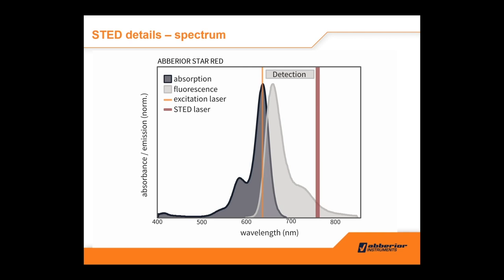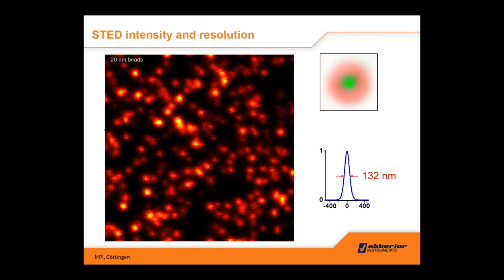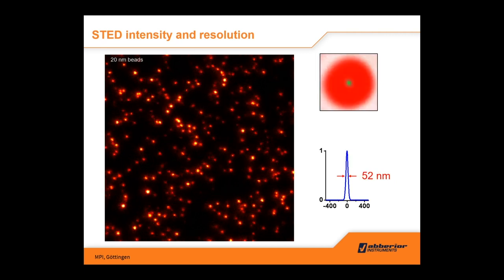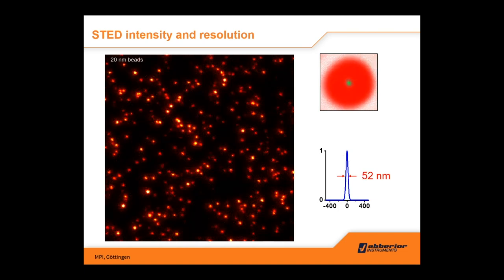In this configuration you can also add a second dye, for example a red dye like Alexa 594 or STAR 580, with a different excitation laser at maybe 560 or 590 nm, and also deplete them with the 775 nm STED laser. So you get a two-color STED image with only one STED laser. The beauty of STED is that you can freely tune your resolution. If you turn off the STED laser, you're imaging in confocal mode. These are 20 nm beads imaged without STED — basically confocal. If you turn on the STED laser a little bit, you already see resolution improvement, and cranking it up all the way lets you see the 20 nm beads at around 52 nm size. Depending on your experiment, you can choose your resolution by choosing the laser power.